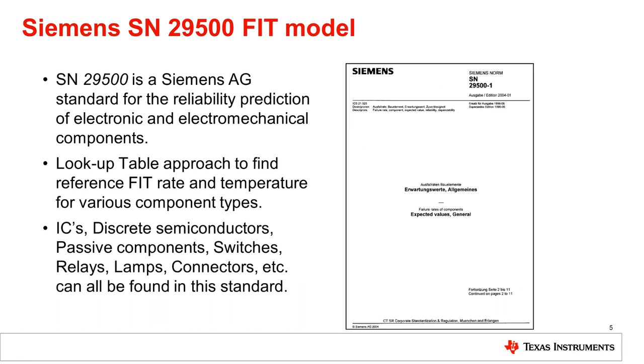Siemens SN29500 is a Siemens AG standard for the reliability prediction of electronic and electromechanical components. It's a lookup table approach to find reference fit rate and temperature for various component types. ICs, discrete semiconductors, passive components, switches, relays, lamps, connectors, etc. can all be found in this standard.